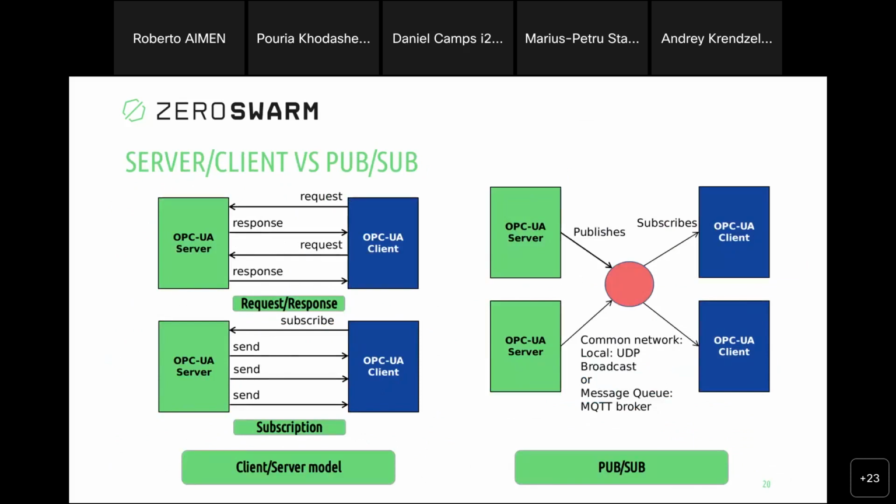So first of all, the communication there doesn't need to go between OPCUA client and the server for the PubSub. It goes mostly between servers, let's say. So you have a server which is doing publishing, and the server which is doing subscription is just creating a sort of channel of communication between them. They are creating a PubSub connection between two servers. And of course, you may do lots of configuration of data and so on. I presume the best link here is the one on overall PubSub aspects.